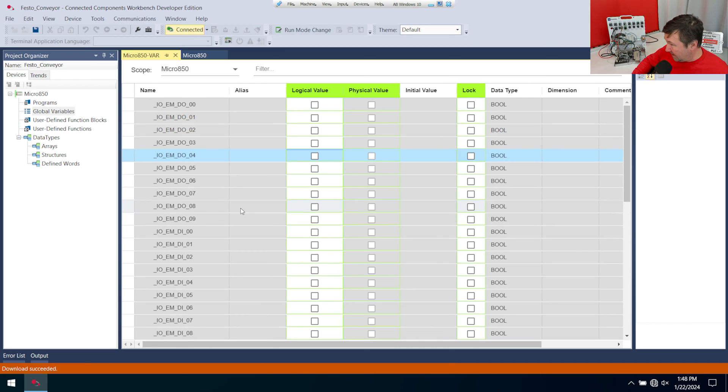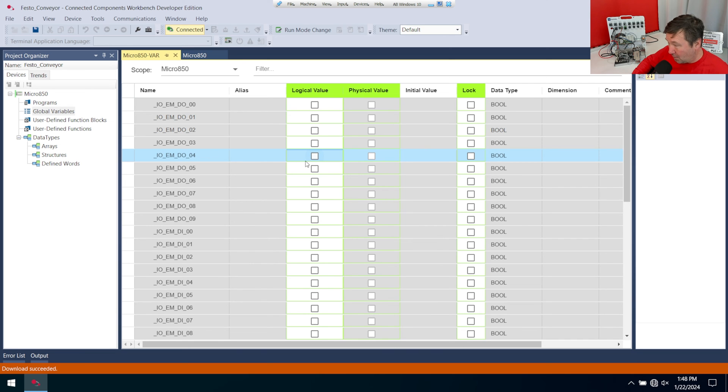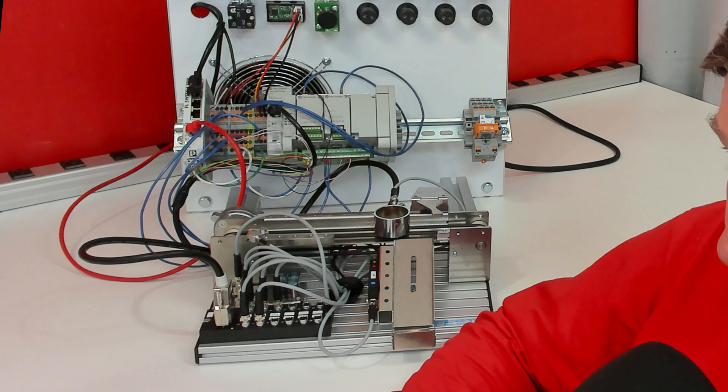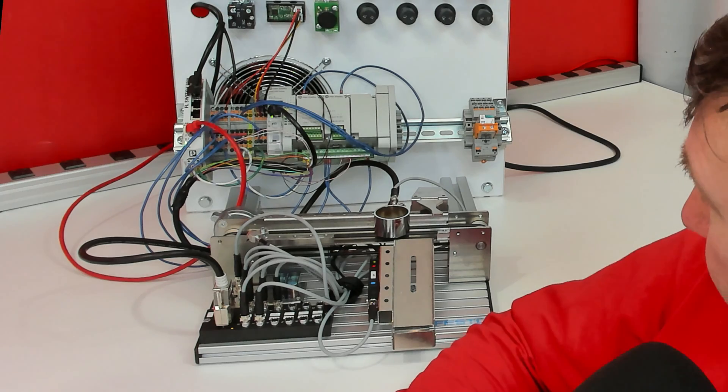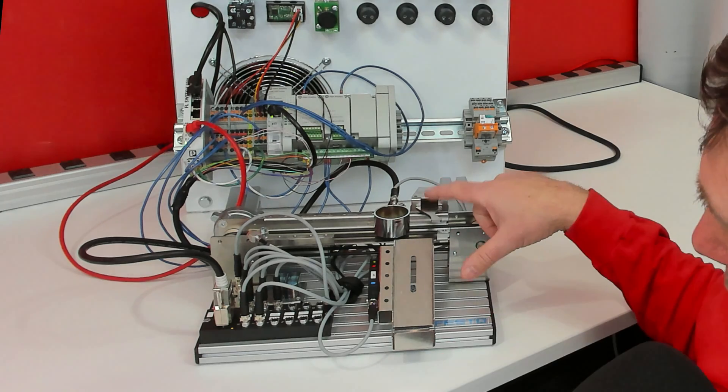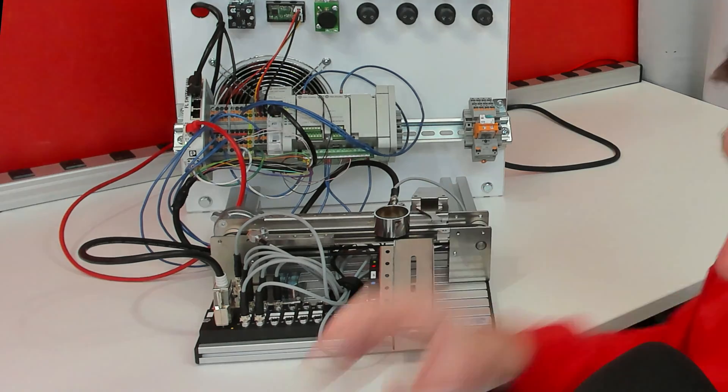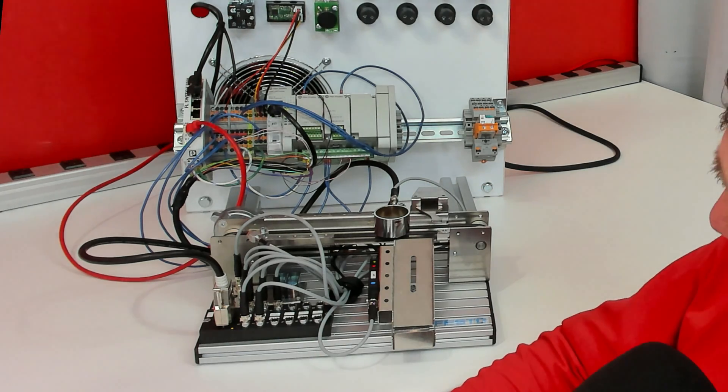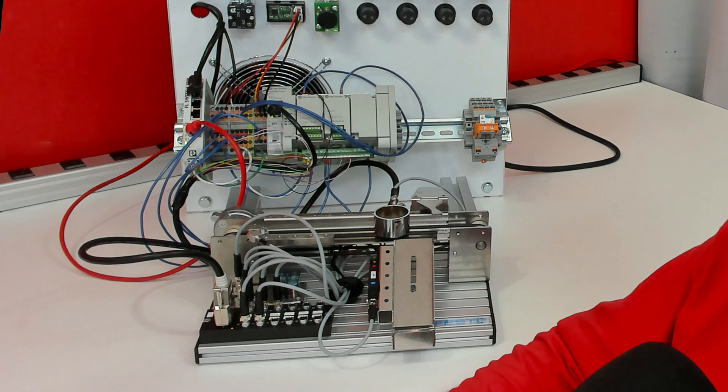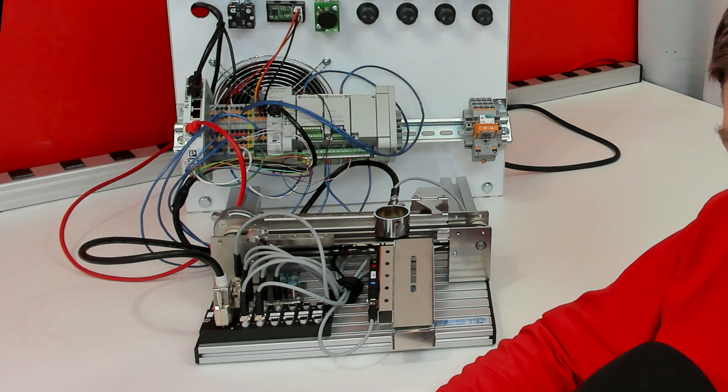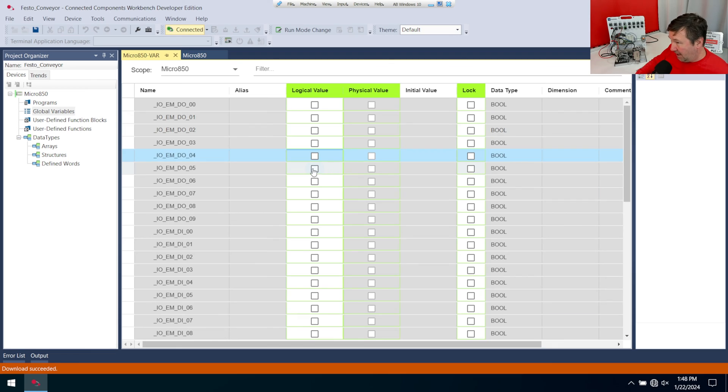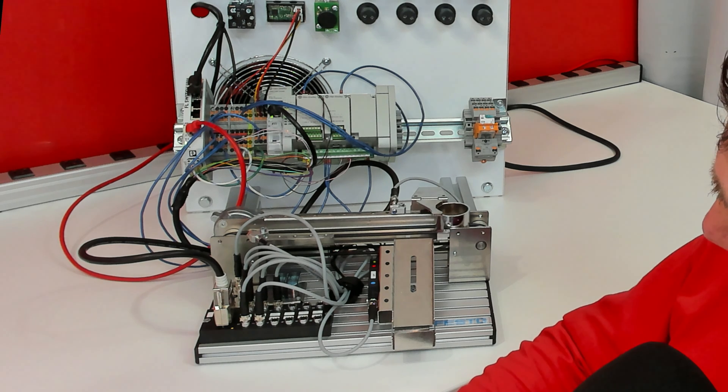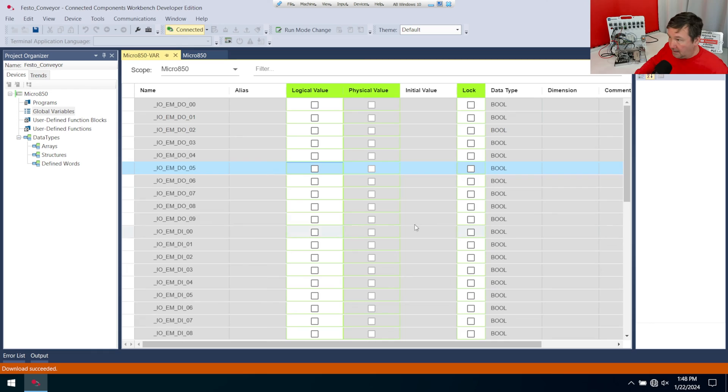Now let's go up and test our outputs. So our first output was wired to output four. And if I check the box on output four, our solenoid comes down. And if I uncheck the box, it goes up. Next, if we check the box on output five, the conveyor runs forward.